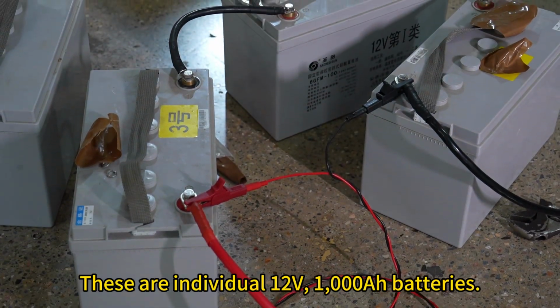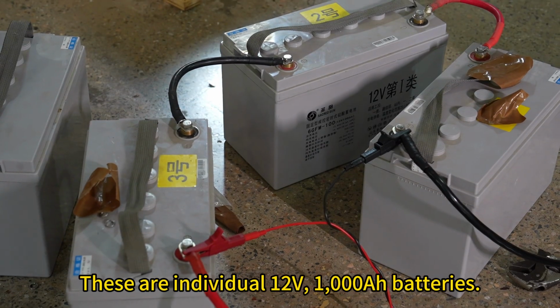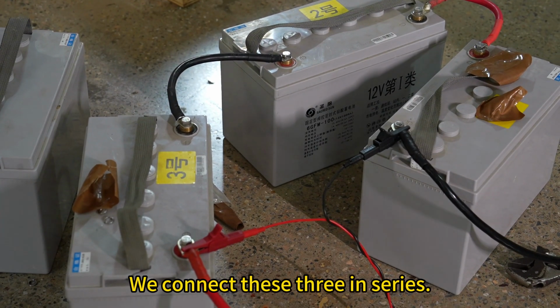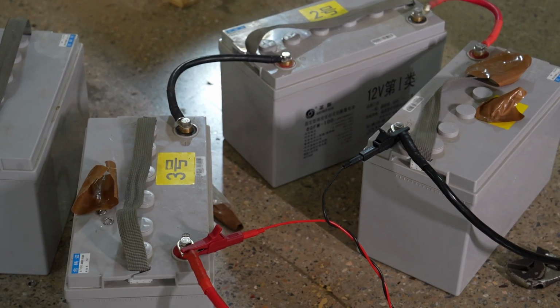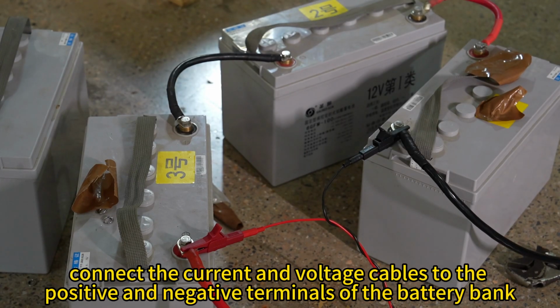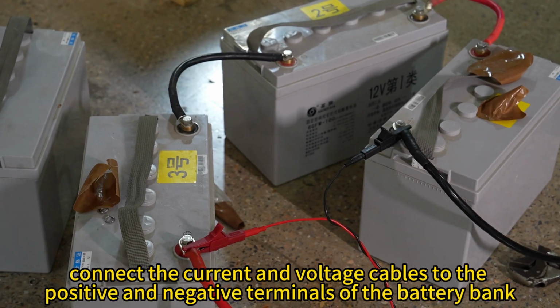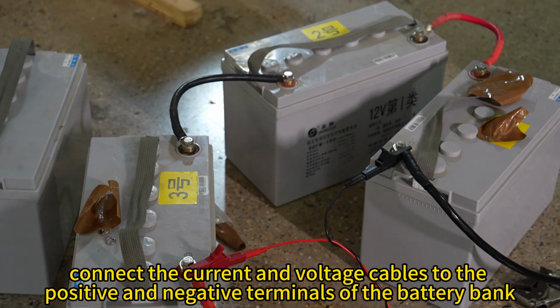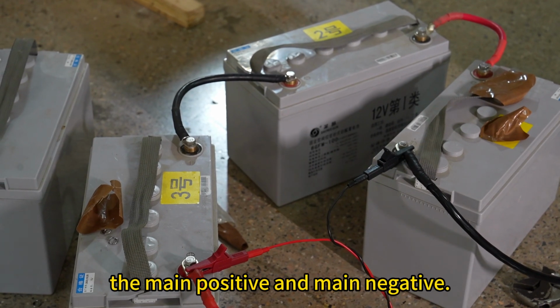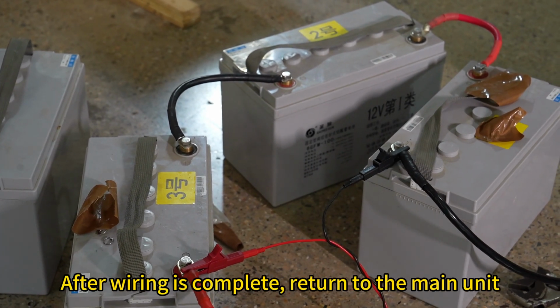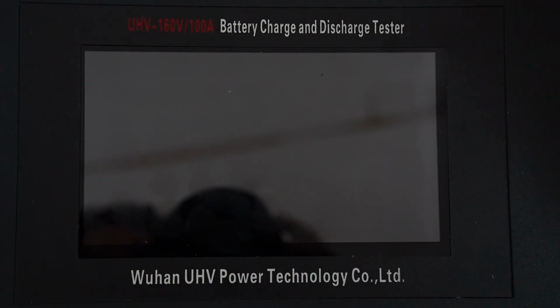These are individual 12 volts, 1000 ampere-hour batteries. We connect these three in series. As just mentioned, connect the current and voltage cables to the positive and negative terminals of the battery bank, the main positive and main negative. After wiring is complete, return to the main unit. Power on the instrument.